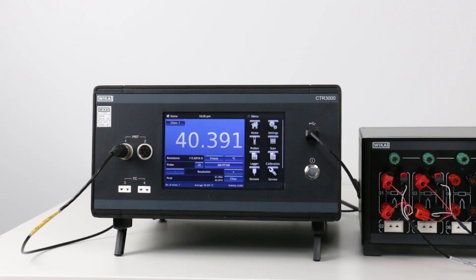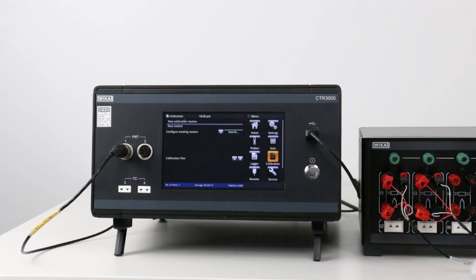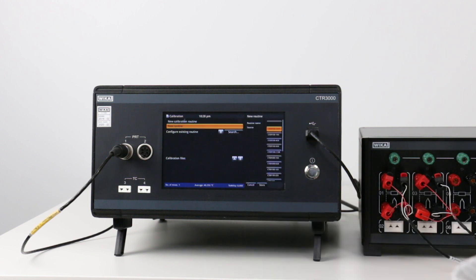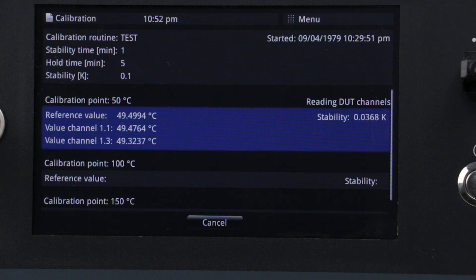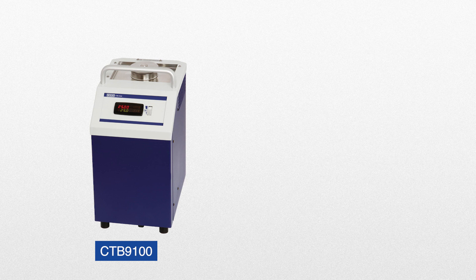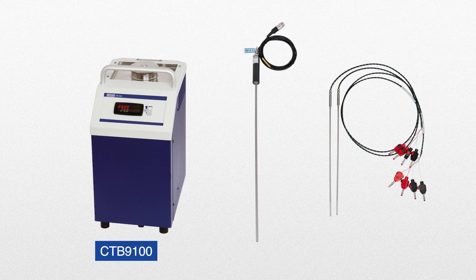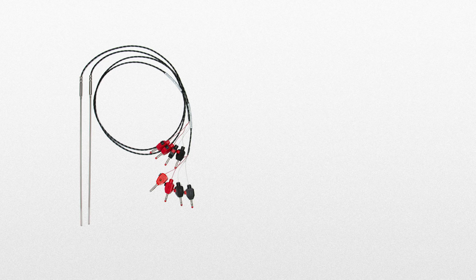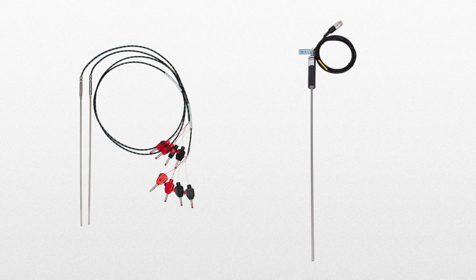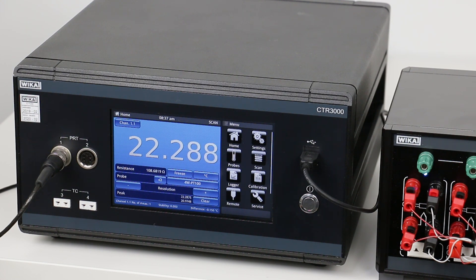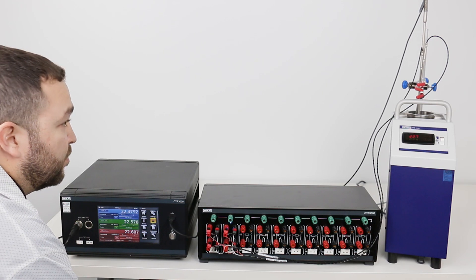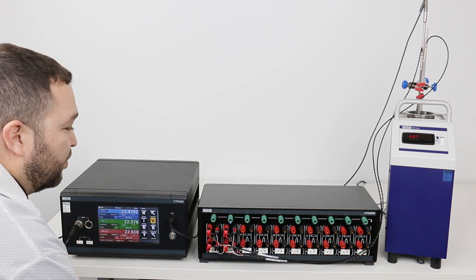It can control the temperature of the bath or dry well in a user-defined test sequence that automatically controls the timing and set points for calibration. The CTR3000 also records the data for reporting. The CTB9100 provides a stable temperature source for the reference probe and probes under test. In this calibration, two RTDs are calibrated using the reference probe. We will now show how the CTR3000 provides a complete measurement and control interface for calibrating RTDs, thermocouples and thermistors, or for simply making high accuracy temperature measurements.